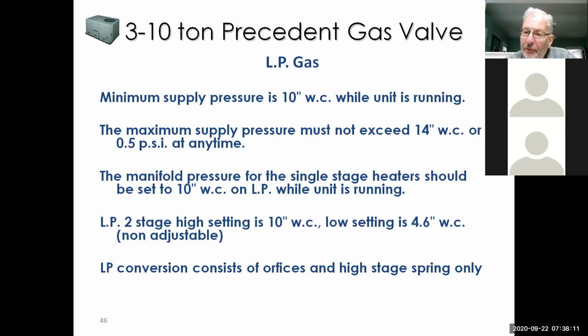The 4.6 is really non-adjustable. So when you set the high pressure, the low pressure should follow it. I have not heard of any issues with it not doing that. I have had guys try to adjust the low fire, and you can get yourself some trouble if you do that, and it doesn't work just right. These things will soot up.